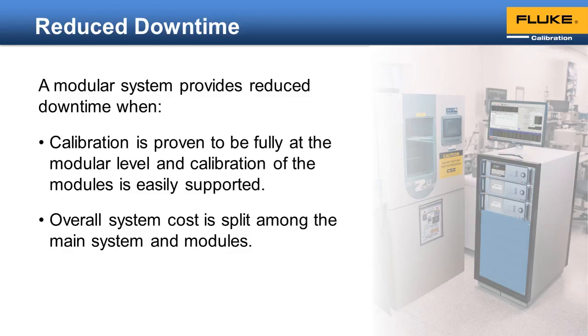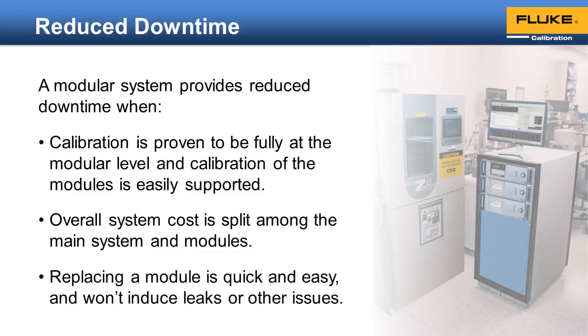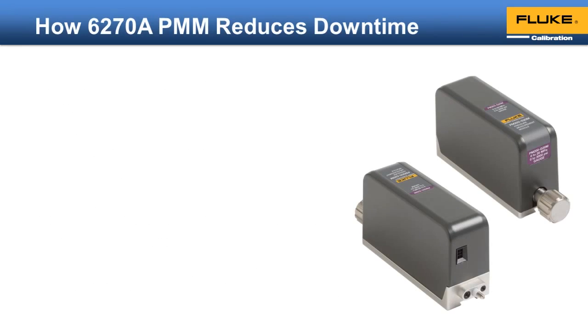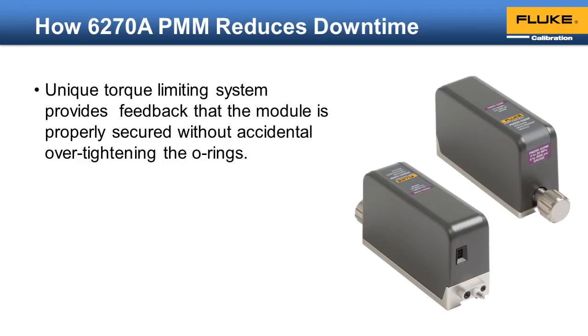When done wrong, modularity can be a detriment to the uptime of a system. If removing and installing a new module results in leaks, then you can end up with more downtime, not less. What causes leaks? Leaks can occur if exchanging a module requires disconnecting pressure connections on the back of the instrument, or if the internal installation of the module doesn't provide binary feedback that the module is properly installed. How does the 6270A reduce downtime? Its unique torque limiting system gives you feedback that the module is properly secured, so you don't have to worry about accidentally over-tightening the O-rings.